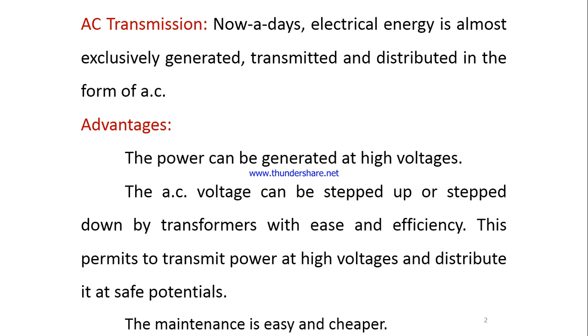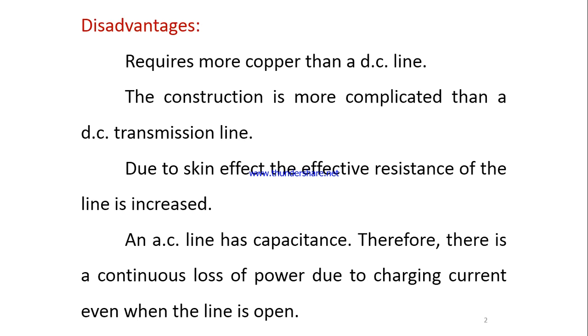First, AC transmission. Normally all our electric systems in India use AC transmission. Advantages: the power can be generated at high voltages, it can be stepped up or stepped down depending upon our conditions, and we can have safe potentials for distribution. The maintenance is easy and cheaper. While considering disadvantages, it requires more copper than a high voltage one, or when compared to a DC transmission line. Construction is complicated, there is skin effect, and it has capacitance and inductance, due to which charging and discharging may take place.